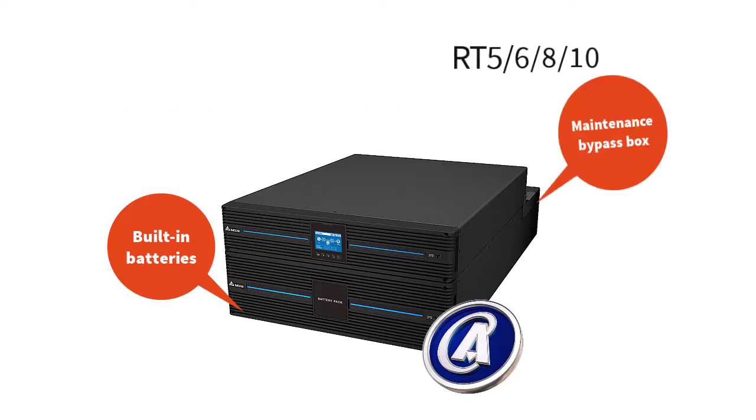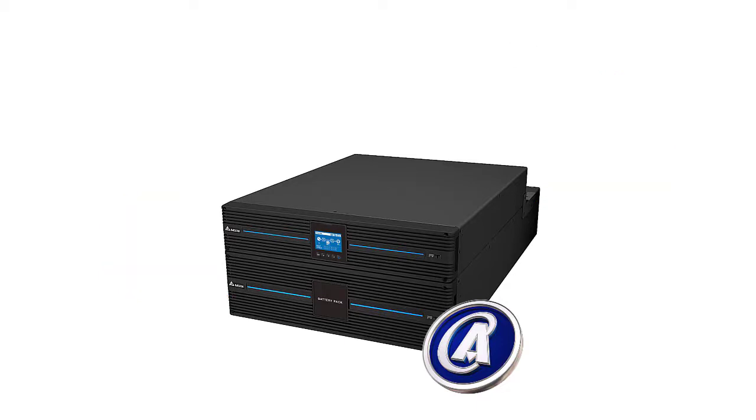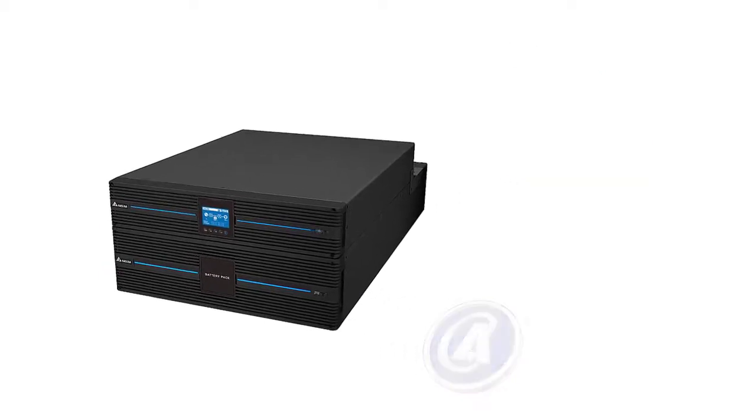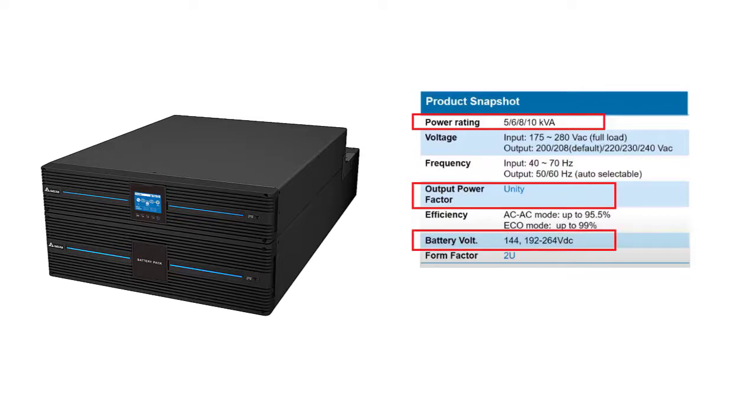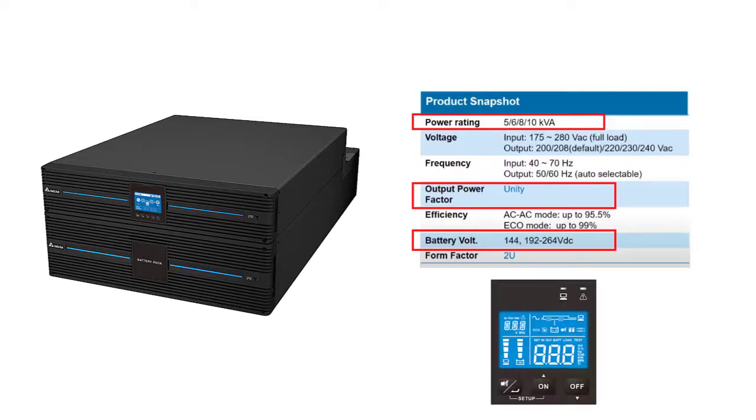The maintenance bypass box is built in at the back of the UPS. These units are now unity factor, giving you exact five, six, eight or ten kilovolt ampere with extreme high efficiency. There is now great flexibility in the battery voltage. Any of these models can now use a standard 144 volts, which is 12 batteries in a string. This flexibility brings great savings to the consumer, and the entire battery configuration can be done on the front LCD panel.